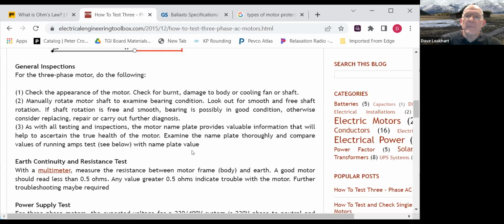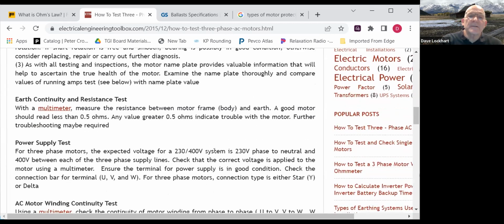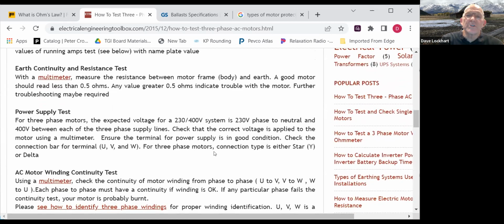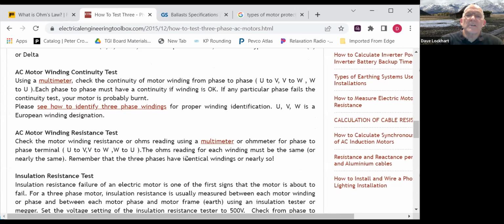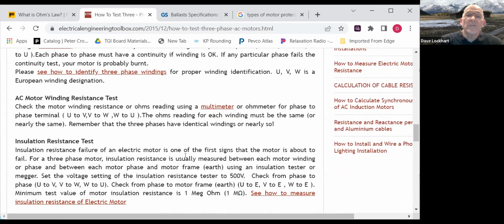As in all testing and inspections, look at your motor nameplate so you understand the voltage and what the amps require. Then you can apply Ohm's law to make sure you get the proper resistance on your windings. They also talk about using your multimeter to check the different phases and windings in the motor, making sure they're okay, and checking to ground. Sorry, folks. It talks through that checking. Also for checking insulation resistance.